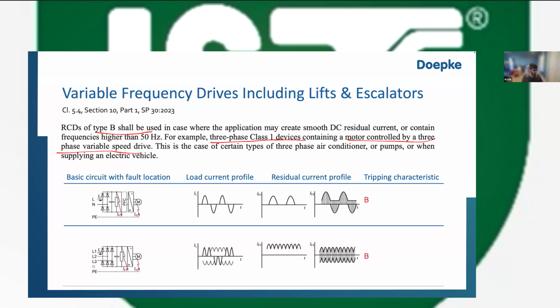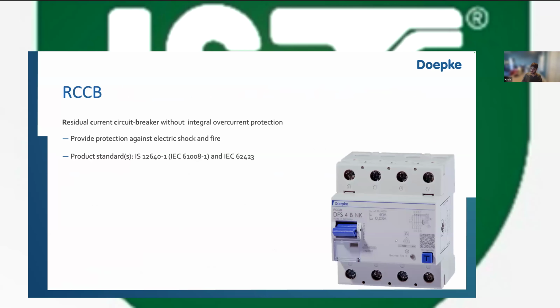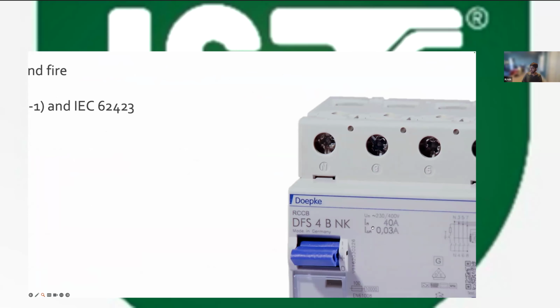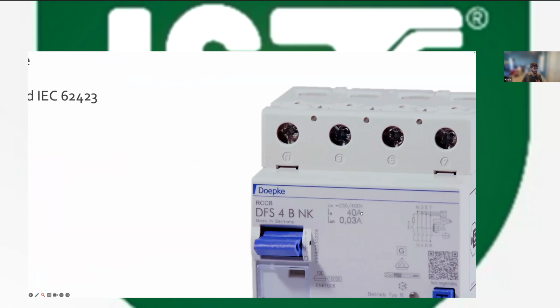Okay. So the first thing is that for the RCD there are multiple parameters that apply. So let's go back to the picture of the RCD and I will show you what I mean. I don't know if you can see very clearly in this picture, but this RCD is rated to 40 amperes. That is the rated current, and the rated residual operating current is 30 milliamperes, so 0.03 amperes. First thing is if you are using a C curve 63 ampere MCB, this rating has to be at least 63 amperes. So in your case you would specify a 63 ampere rated RCCB.